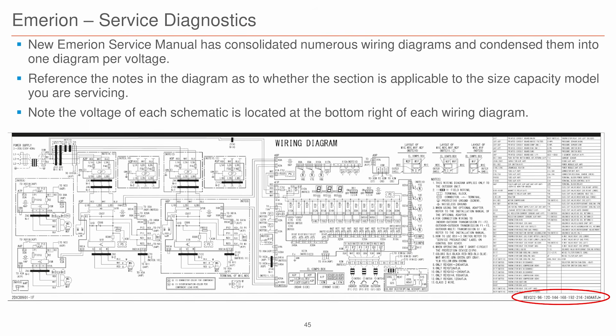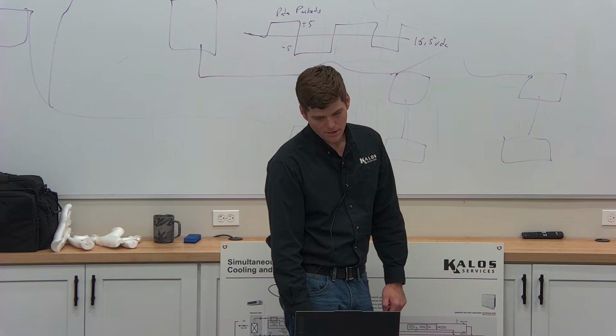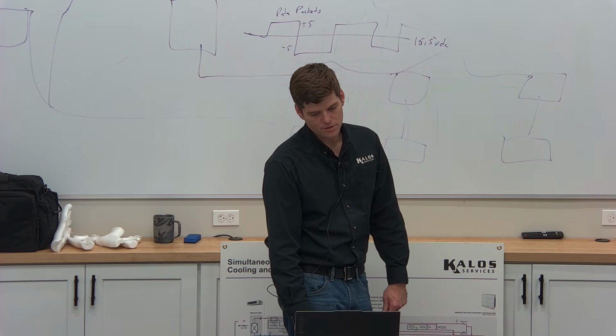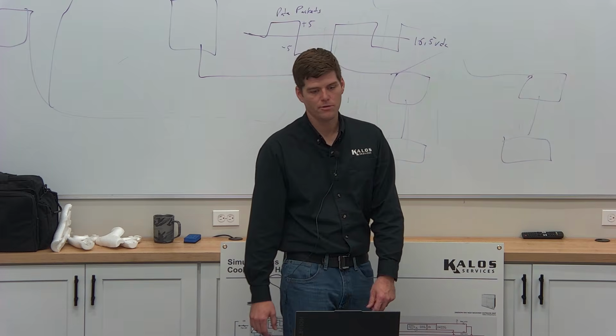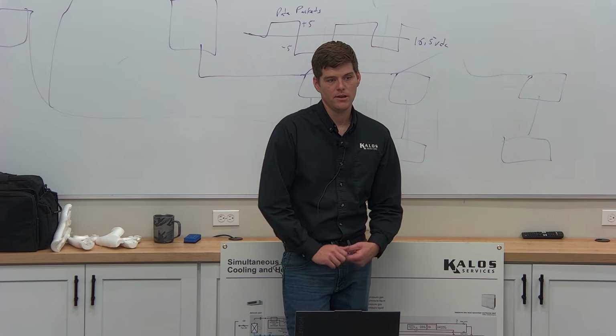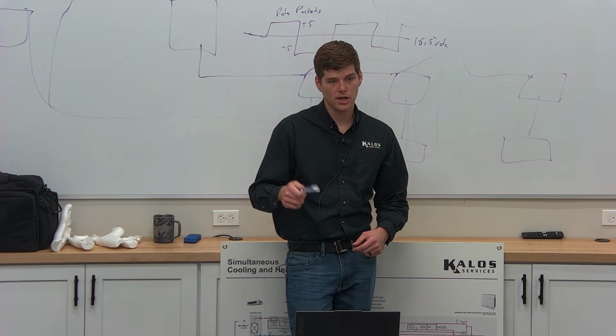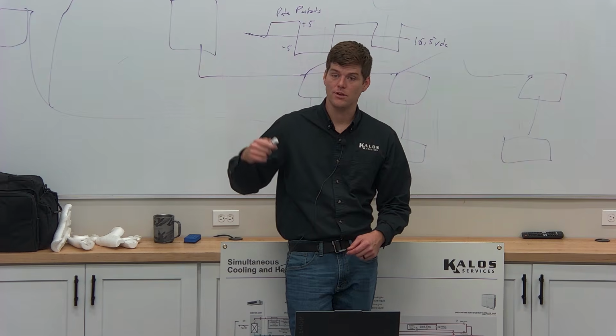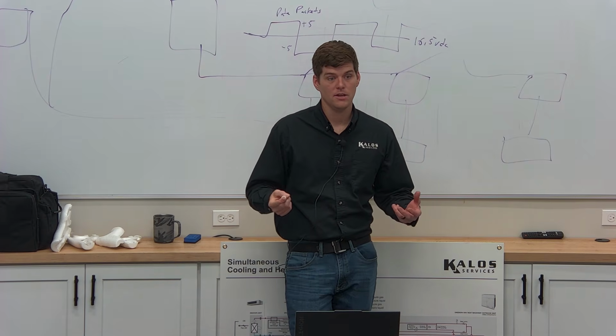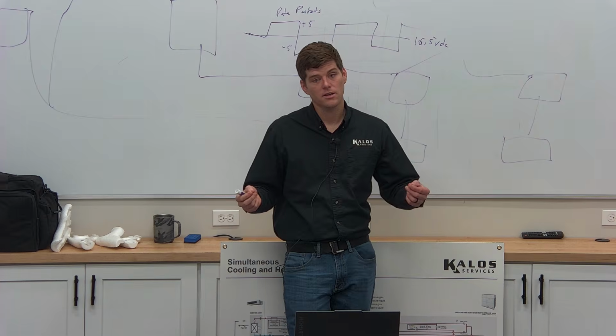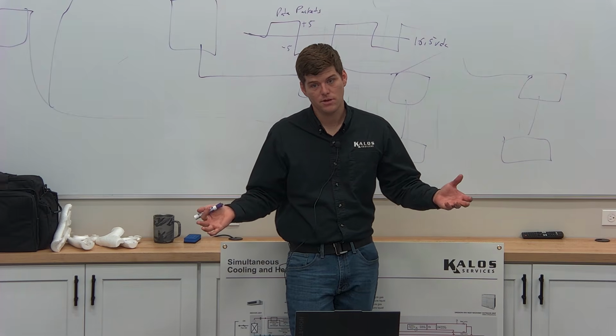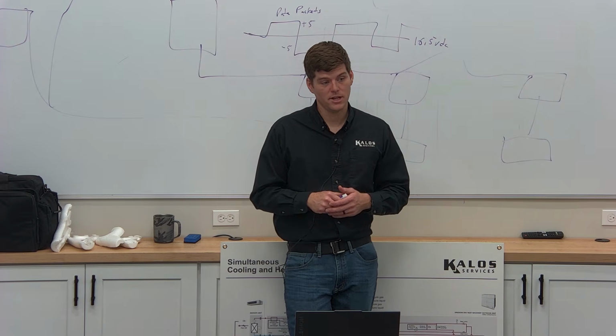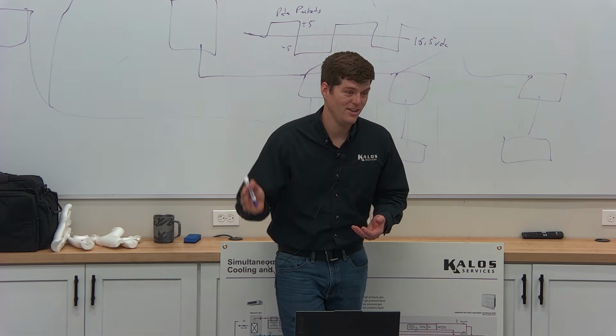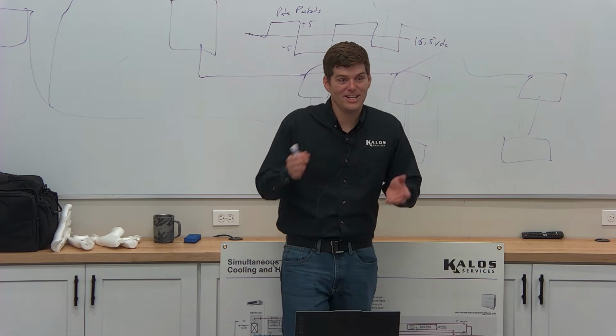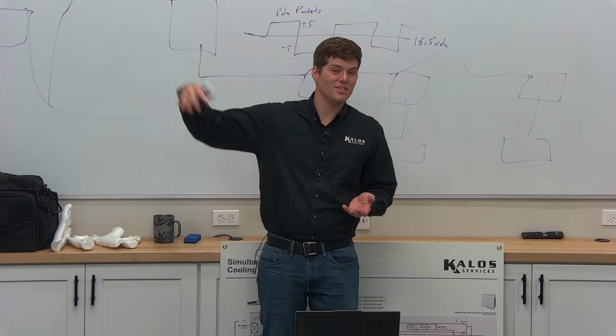But this is a typical wiring schematic for a VRF system. Should be very familiar for you. And we'll walk through that with troubleshooting. The other thing I want to note, guys, for VRF systems, you don't just go to a VRF service call, put a laptop on it, record 5 minutes of data, and then leave, right? These are systems that are constantly changing valve pulses, temperature, revolutions per second, compressor speed. Things change so quickly, but they also change very slowly. And so you can't just go to a system and record 20 minutes of data. The unit may not even start in the 20 minutes, right?